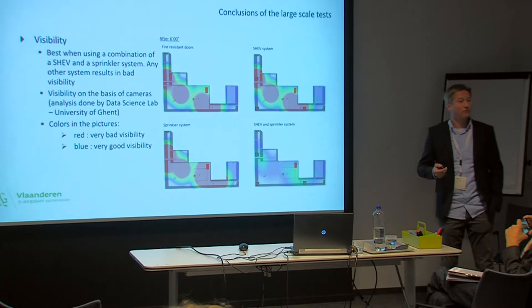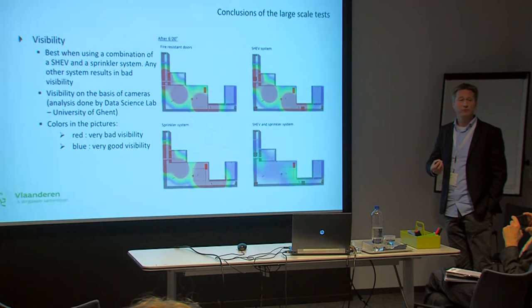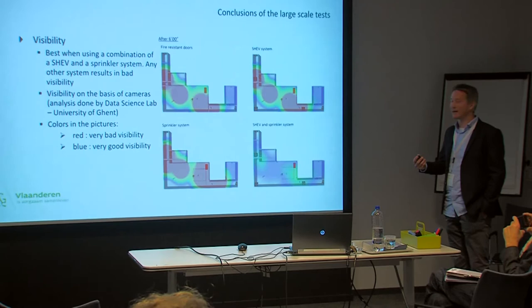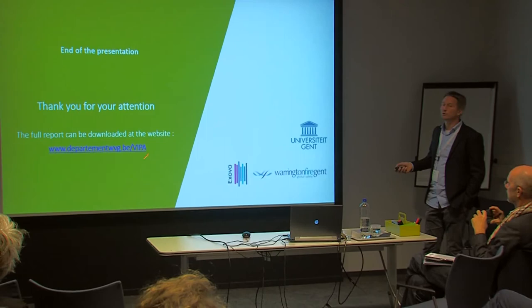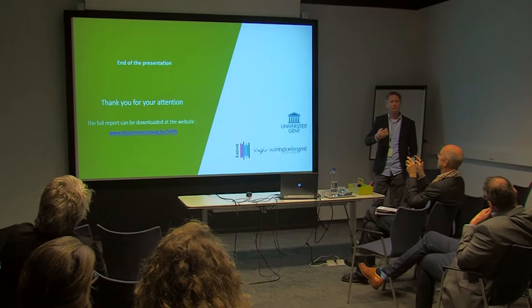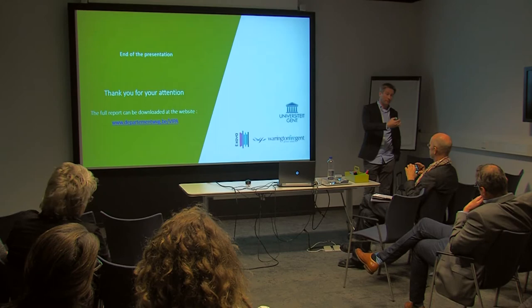And as a conclusion of this presentation, I would like to say that fire-resistant doors on their own are not good. Only a sprinkler is not good. Only a SHEV system is not good. It's a pity that I don't have more time, but in phase three, and therefore I think you should read the study, there are a lot of measures for elimination of pressure buildup, to prevent smoke propagation, and so on. They're all clearly stated: what you have to do in case of that scenario.